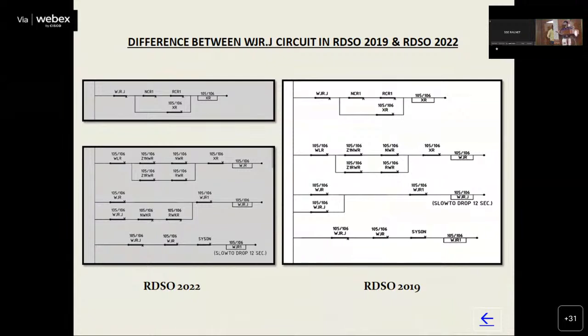But now, what will happen? With this logic, the window is of 12 seconds, but this will cut off WJR.J supply once the indication is available. So now with this logic, there is no need to extend supply through NC or RC contact. Directly through the logic itself, once the point is set, the supply will be cut off.